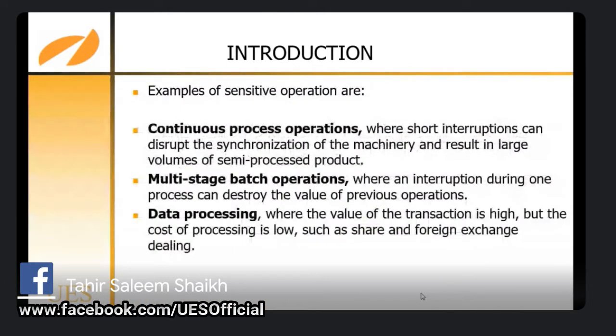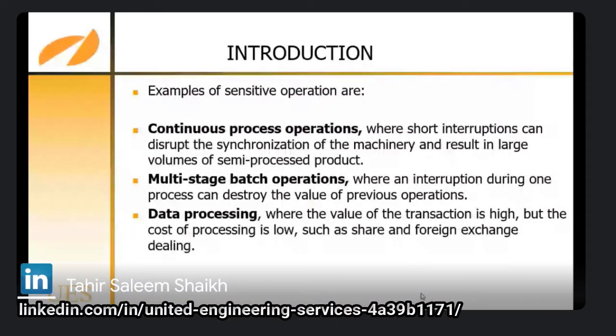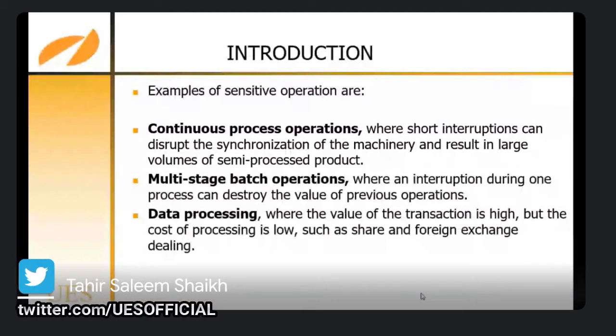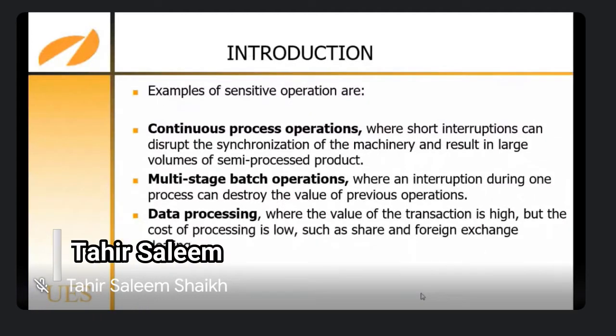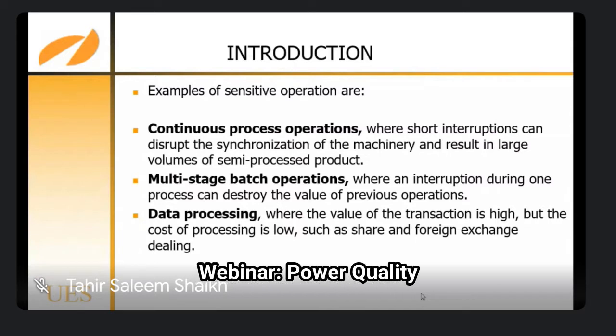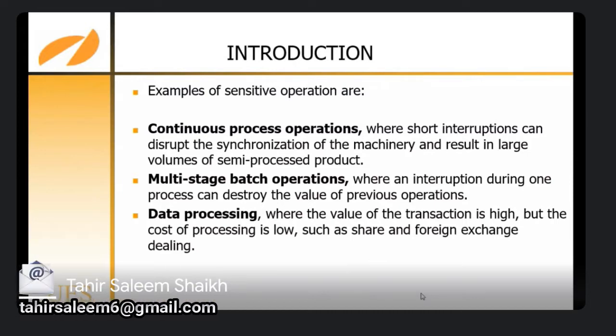Like my plant, it was a continuous process operation, where a short interruption can disrupt the synchronization of the machinery and result in large volumes of semi-processed product. Then multi-stage batch operation: this is an industry where an interruption during one process can destroy the value of previous operations. Then data processing, where the value of the transaction is high but the cost of processing is low, such as share and foreign exchange dealings. This will also damage your electronic equipment.